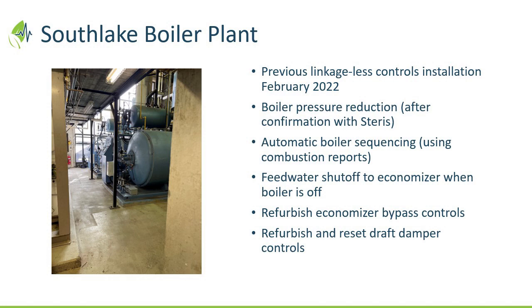And is there any compatible linkageless control? Because when you're running the Thermogenics boiler, there's quite a bit of different models available in the market. So with the Thermogenics boilers, what kind of linkageless control do you recommend? You can put any on. And I think that's an excellent question, because I don't want everyone to think you've got to put 6 figures in to get a linkageless system. There's more to that decision. Depending on the age of your boilers and the flame safeguard that's in there, there are bolt-on packages that are half the price to still get fuel-air ratio control. So you can achieve the same results, but it's very specific to what your current system has. There are several brands that you can utilize, and we've used them all. And I think, John, your installation was 125K, I remember.